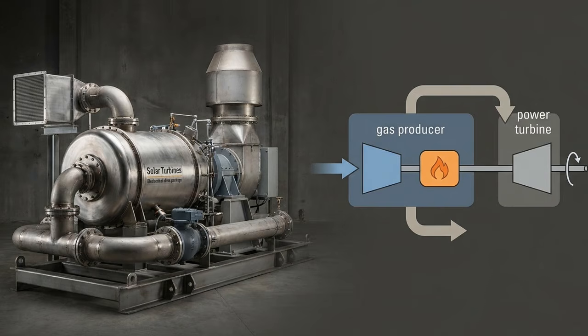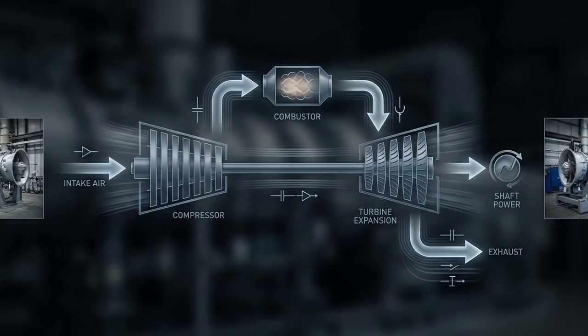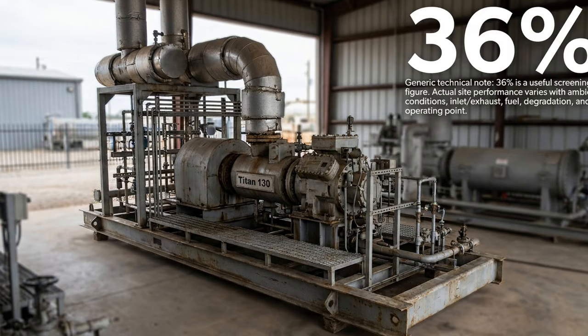The Titan 130 mechanical drive configuration uses a two-shaft concept, a gas producer that makes high-energy gas flow, and a separate power turbine that delivers shaft power. This separation helps match turbine output to variable compressor operating requirements. The basic gas turbine process is intake, compression, combustion, turbine expansion, shaft power, and exhaust. Air is compressed, fuel is burned, hot gas expands through turbine stages, and useful power is delivered to the load or generator. In simple cycle mechanical drive duty, the Titan 130 is commonly associated with approximately 36% thermal efficiency.